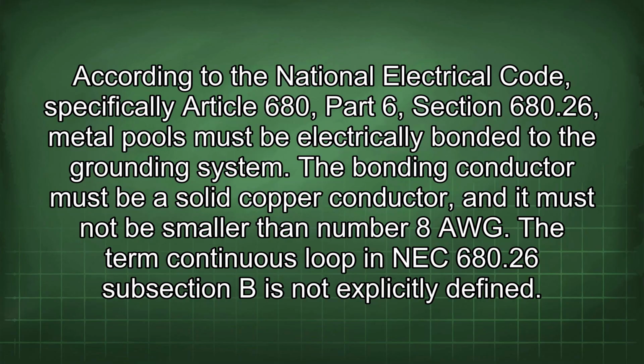According to the National Electrical Code, specifically Article 680, Part 6, Section 680.26, metal pools must be electrically bonded to the grounding system. The bonding conductor must be a solid copper conductor, and it must not be smaller than number 8 AWG.